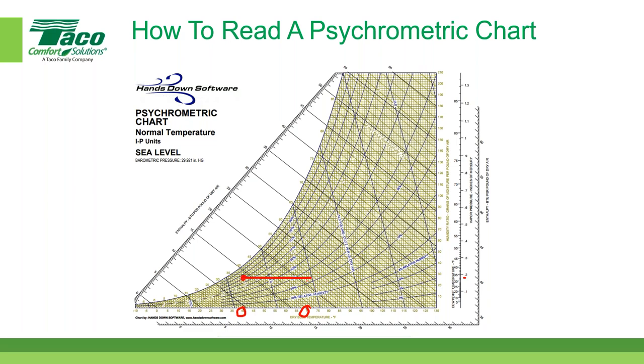I'm heating the air up from 40 degrees Fahrenheit to 70, and I'm moving from left to right on the psychrometric chart. Whenever I draw a horizontal line from left to right, that's called sensible heating, and I can plot that out on a psychrometric chart. Right now we said it was 40 degrees Fahrenheit dry bulb, and I think 35 degrees Fahrenheit dew point. Whenever the dew point temperature remains constant, that's sensible heat. I'm not adding or removing any moisture from the air. Pretty cool stuff, huh? I can see why that's the easy one. That's the easiest one that we have.